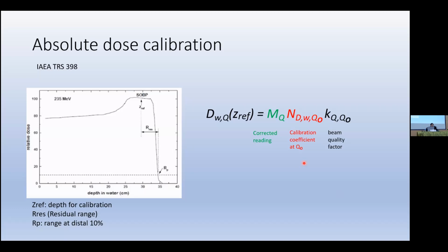So for our system, since we did the calibration, we did from 10 cm to 20 cm in the cube, in the middle. So the residual range was 5 cm from the middle to there, so it would be similar to us here. That's where we measured, and then did the scan back and forth a little bit because there is the ripple. The issue with the Farmer type chamber is exactly where the effective point of measurement is, so I had to get that average.